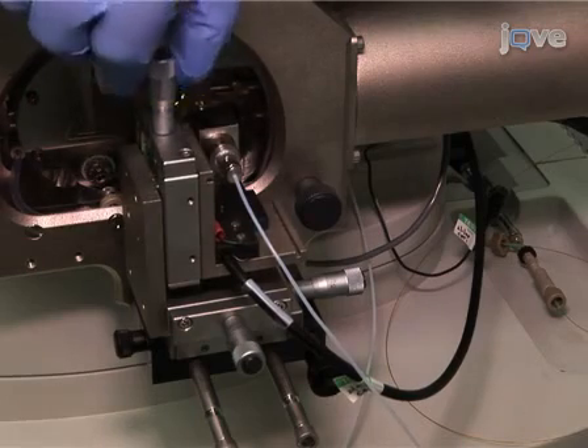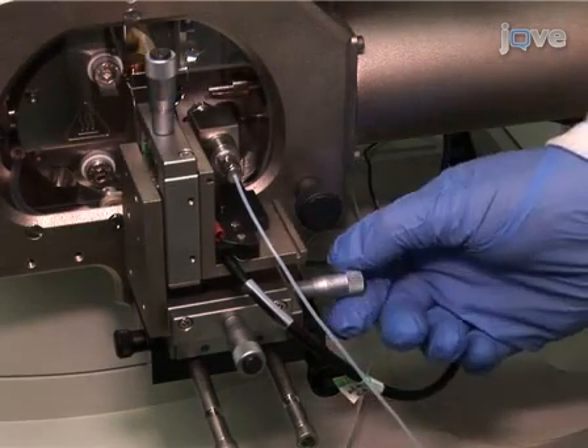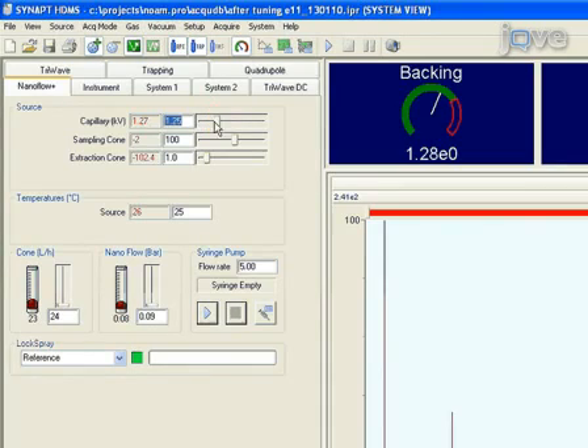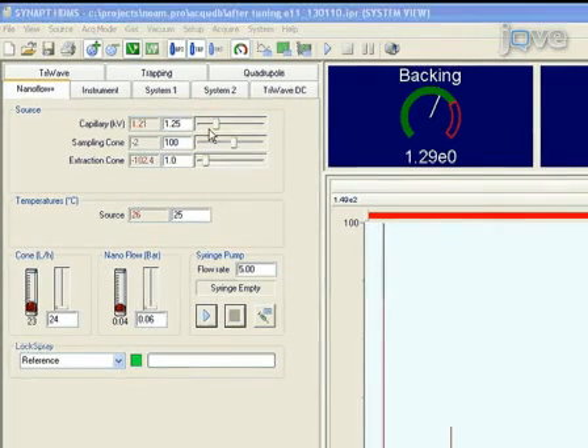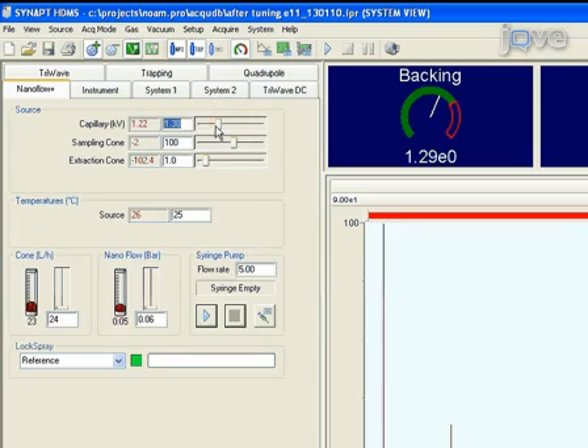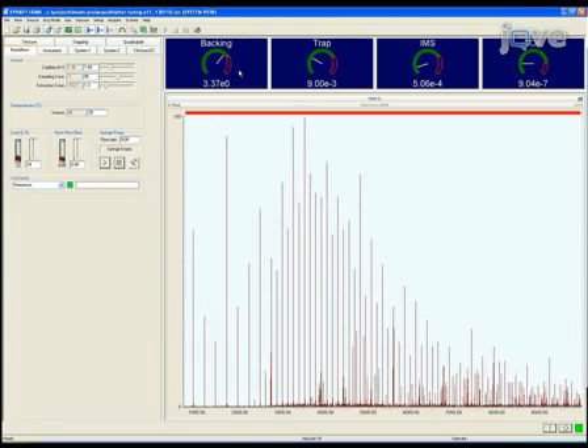Optimize the signal intensity by adjusting the location of the XYZ stage, the capillary voltage, the nanoflow pressure, and the desolvation gas flow. To detect a wide mass range of cesium peak series, the accelerating voltages should be optimized. The parameters used here are capillary 1.3 to 1.7 kV, sample cone 80 to 150 volts, and extraction cone 1 to 3 volts. To optimize the transmission of high-mass ions, which require gentle desolvation conditions, the backing pressure is raised to 5 to 6 millibar in the initial vacuum stage, between the source and the analyzer.